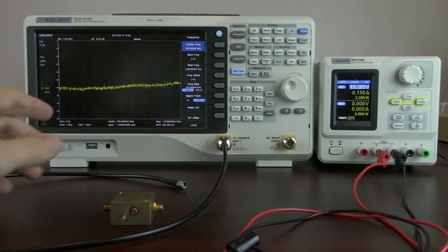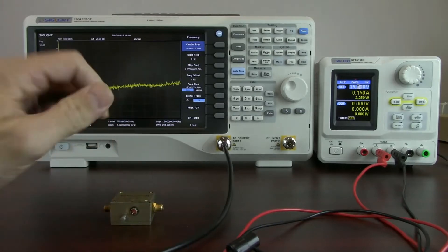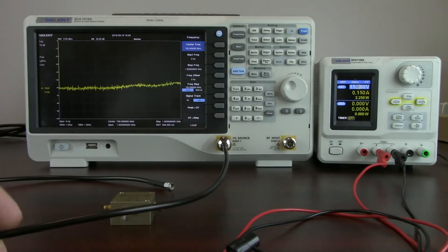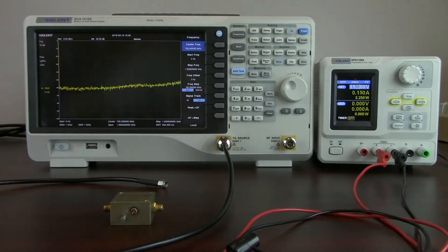So, the first thing that we're going to do is we have an SMA to N type connector here on the tracking generator source output. So the tracking generator source is going to source a particular frequency or range of frequencies.